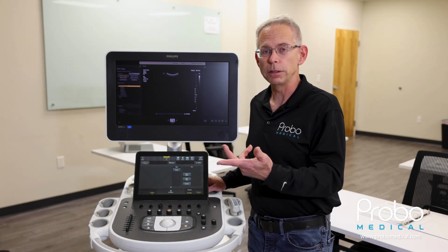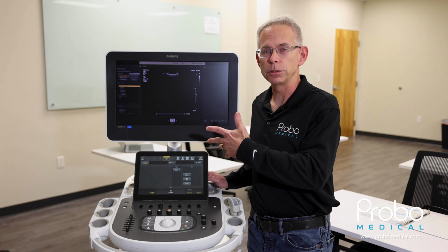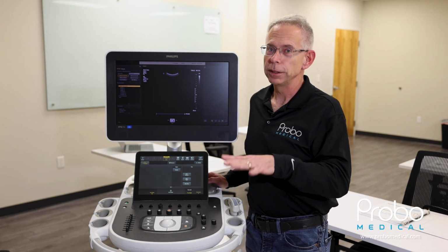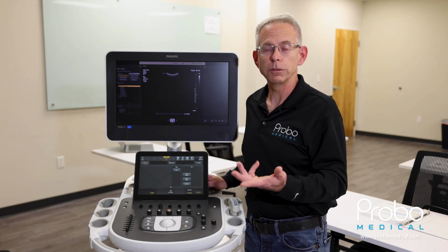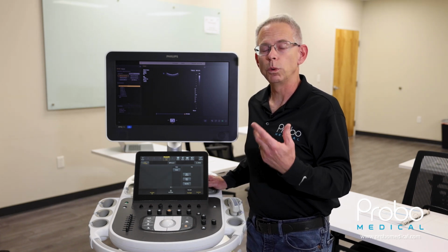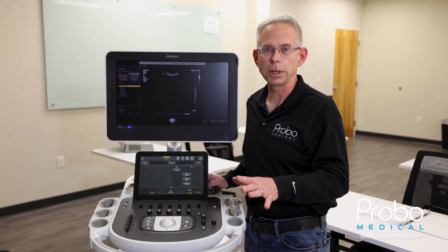In order to do that, you can go in and run the patient database utility. One word of warning, when you do this, you are getting rid of all of your patient data, not just individual patients. So you wanna be sure that this is okay to do.